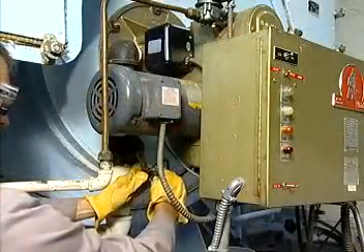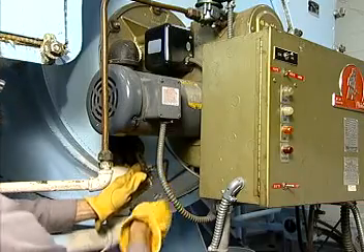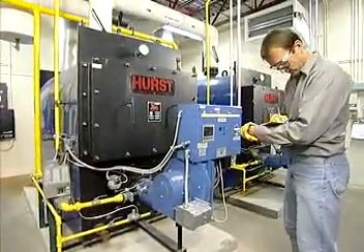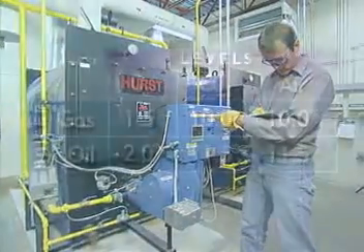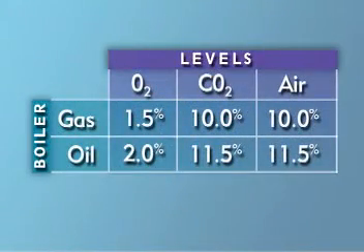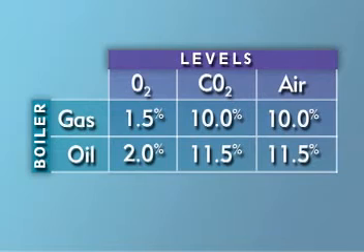Next, adjust the boiler air-fuel ratio controls. While the boiler is still operating at high-fire, adjust mechanical air-fuel linkages so that they maintain the desired air-fuel ratio. If your boiler is equipped with solid-state excess air controls, adjust the controls to the desired level of excess air. While the level of excess oxygen will vary based on outdoor air conditions, a typical oxygen level of 1.5% with a corresponding carbon dioxide level of 10% is a good target for natural gas-fired boilers. These readings correspond to an excess air quantity of approximately 10%.